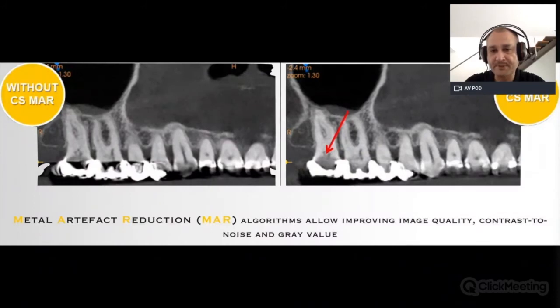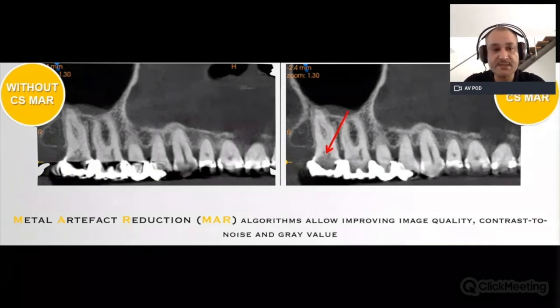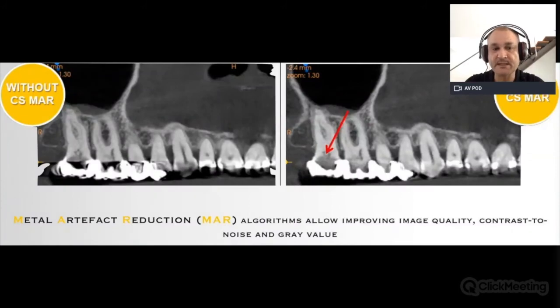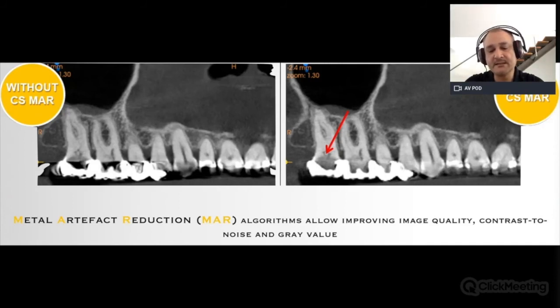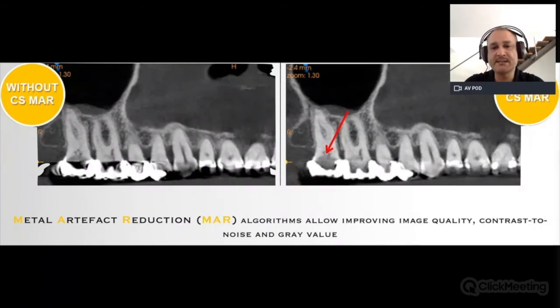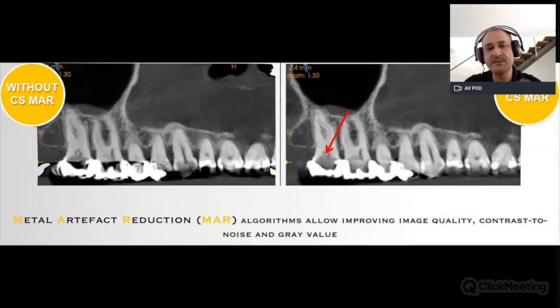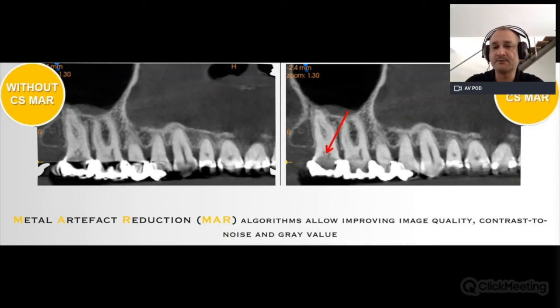Many CBCT machines, like the Carestream machine shown here, have software to reduce artifacts. This software is called Metal Artifact Reduction, or MAR — it's an algorithm that informatically helps make this reduction. However, one should be careful: these algorithms make the picture look much nicer and easier to interpret, but it may not correspond to the real situation inside the mouth because it has been processed computationally.